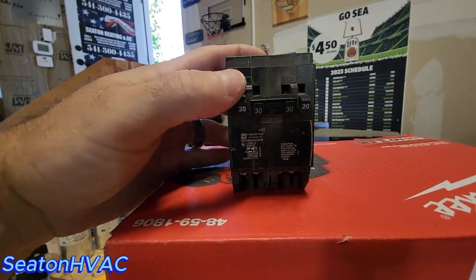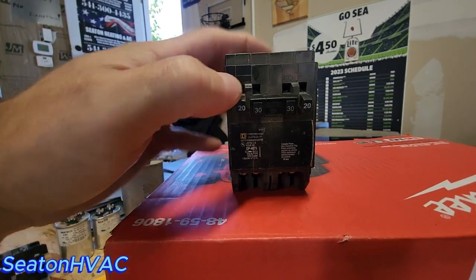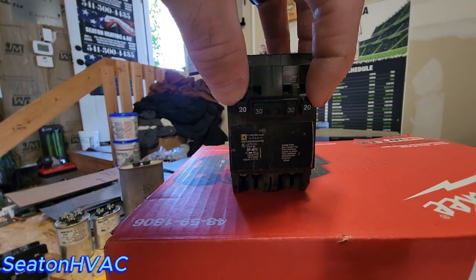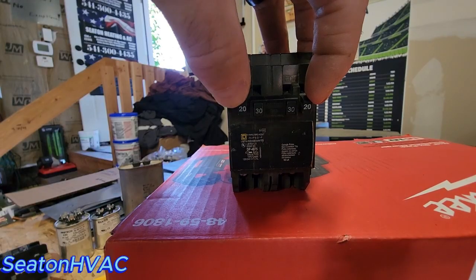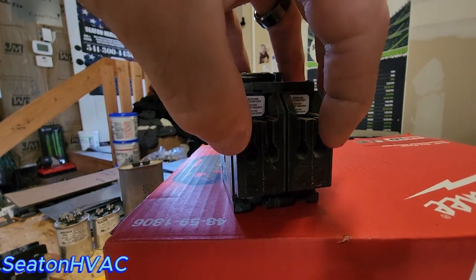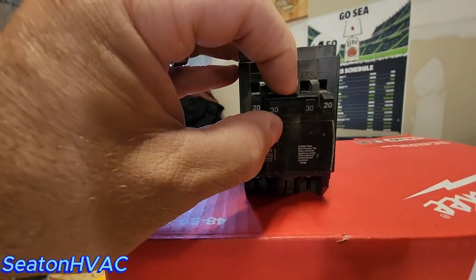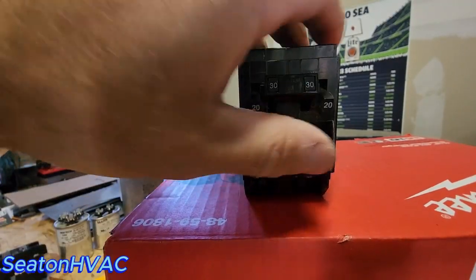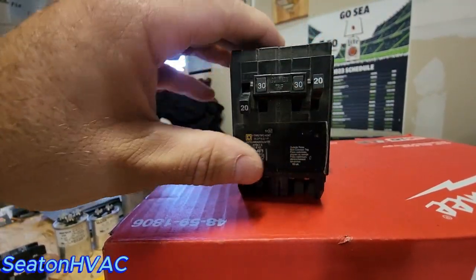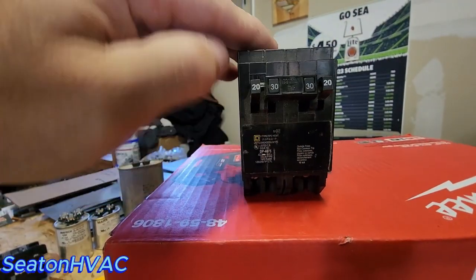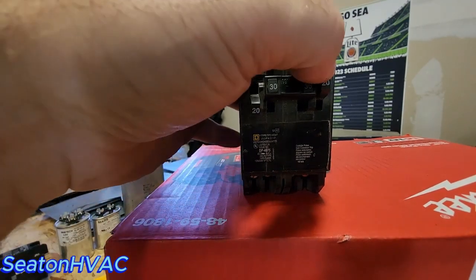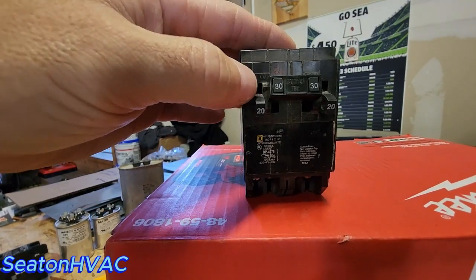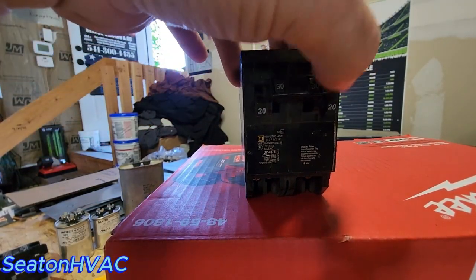This one's a little different. This is what's called a quad breaker. So you have one circuit on the outside, which is a 20 amp 240 circuit, and those terminals are the two outside terminals. And then you have, just like my other one, a 2-pole. They're both 2-pole breakers. You don't want to flip one of these up without the other one. You could. Actually, you can, so I said it wrong. This would have a bar across here joining these.